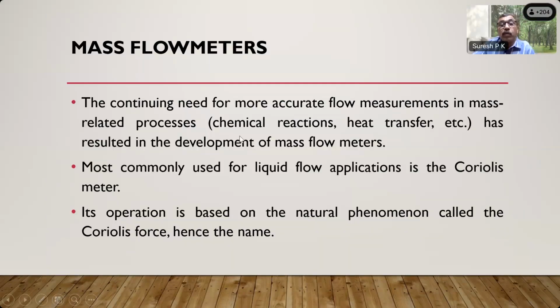Another thing is the mass flow meter. The continuing need for more accurate flow measurement of mass-related processes and chemical reactions has resulted in the development of mass flow meters. The difference between other meters is that generally they measure the velocity, or an indication of velocity, which is again used to calculate the volume flow rate. Here you get a direct mass indication from the meter. It's called the Coriolis mass flow meter. The Coriolis effect is utilized in this meter.